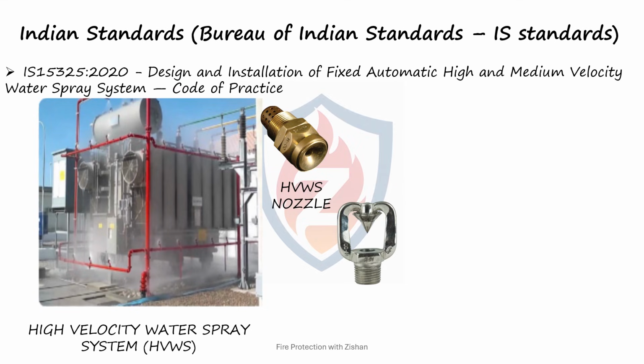In the center, the image shows the nozzles used in these systems. The high-velocity water spray nozzle produces a powerful and directed water discharge for fire extinguishment. The medium-velocity water spray nozzle, on the other hand, creates a spray pattern that provides cooling, exposure protection, and fire control over a larger surface area.